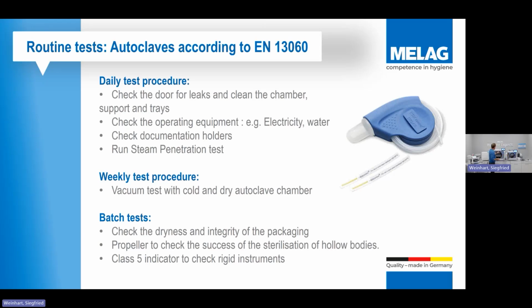You've then got, on a weekly basis for all vacuum autoclaves and S-class autoclaves, something called the VAC test. And the VAC test, we take this one out, it's basically looking at this chamber and ensuring that this chamber hasn't got any microfractures in it. Because what can happen if there's microfractures in here, it can inhibit its ability to pull a vacuum, which then brings its own problems. So it has to be done on a cold chamber.